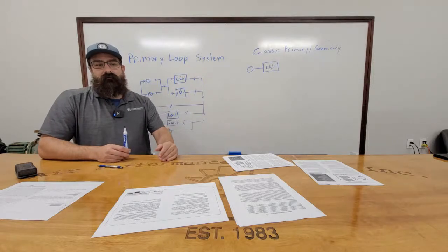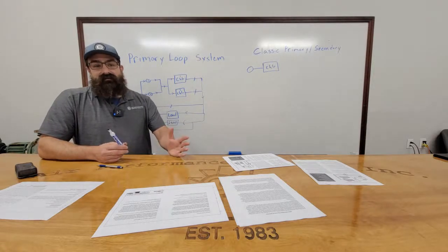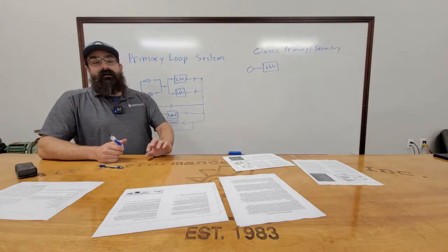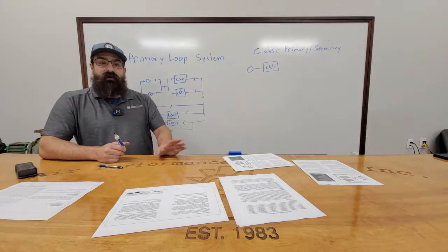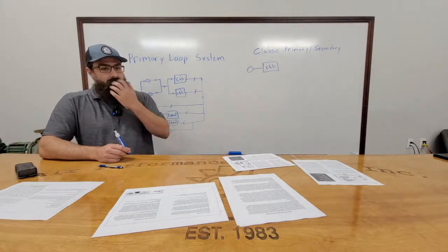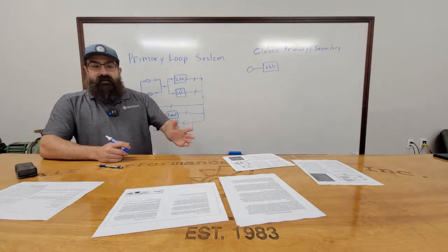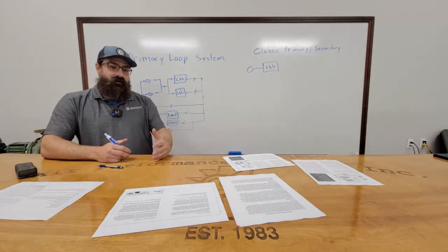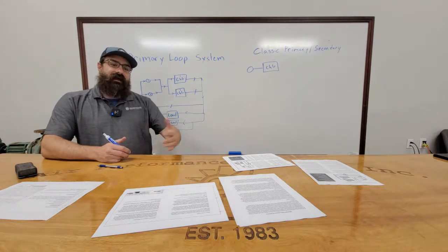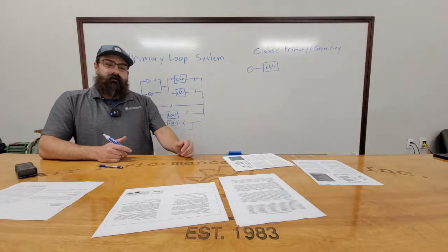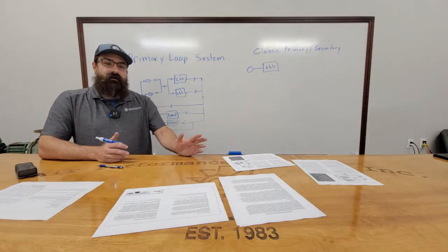What's the normal drop across those coils? These are 18 for some reason. I'm not familiar with all of them. I know they hired an engineer to come look at it and tell them what it needed to be set at, because when they took this building over, there was no documentation. As soon as they bought it, they put in these brand new Carrier chillers. Carrier came out, set the chillers' flow rates right, but then we had to fire both pumps up to get the coils to even make like 60 degree water. I mean, air. They were struggling.